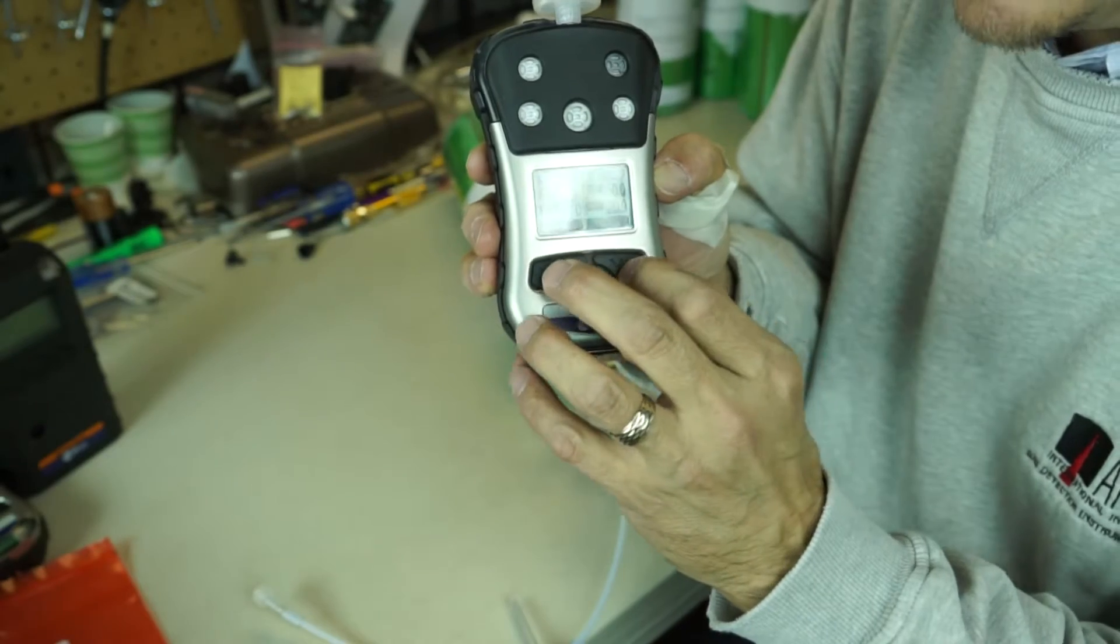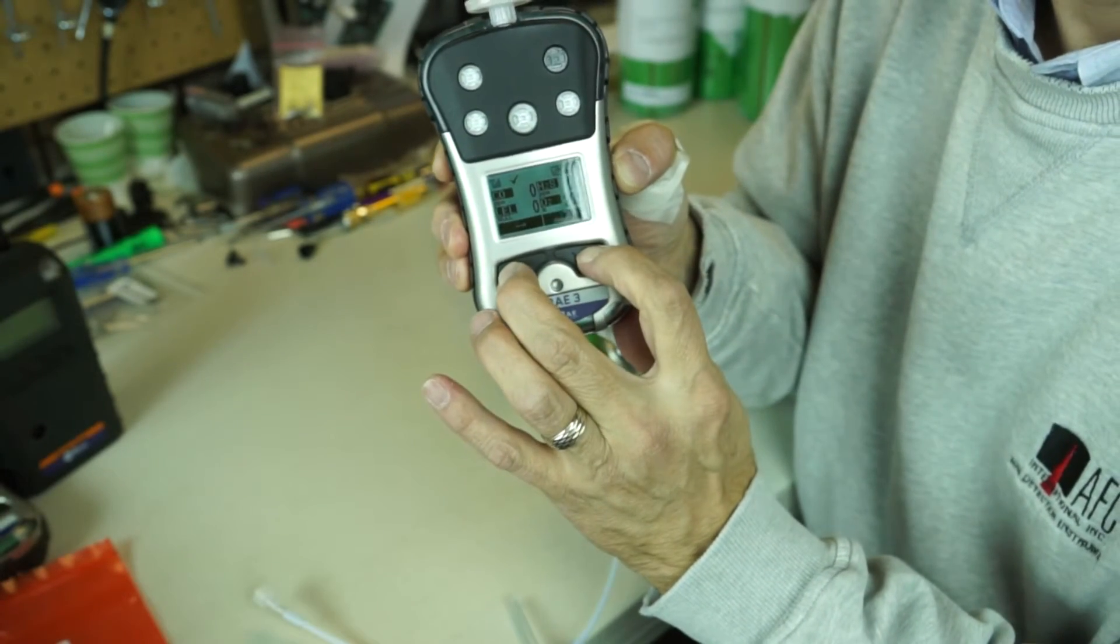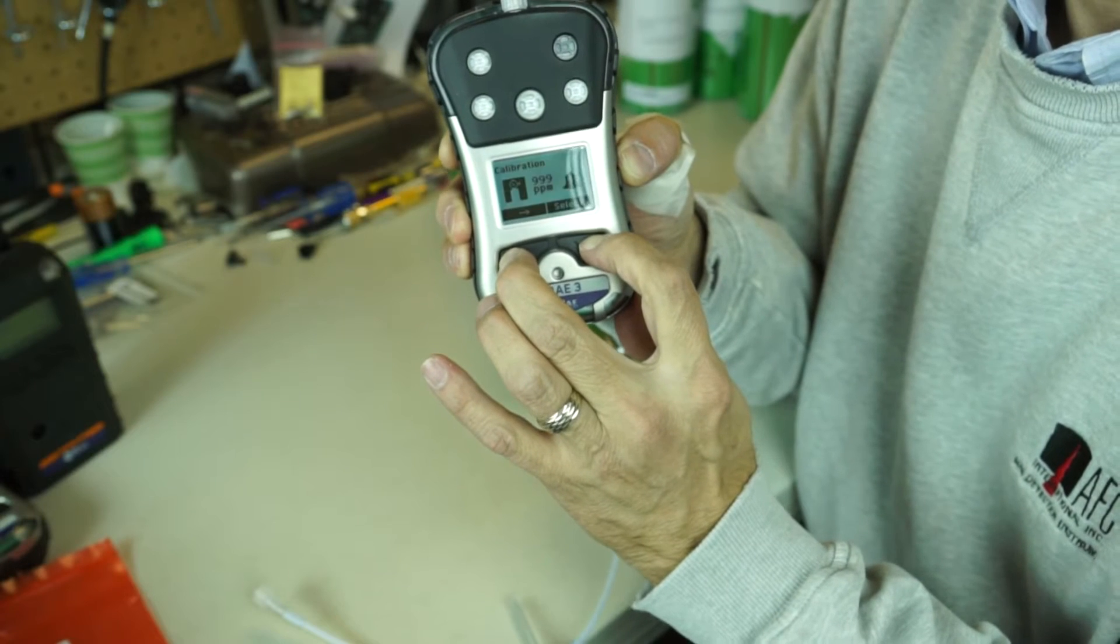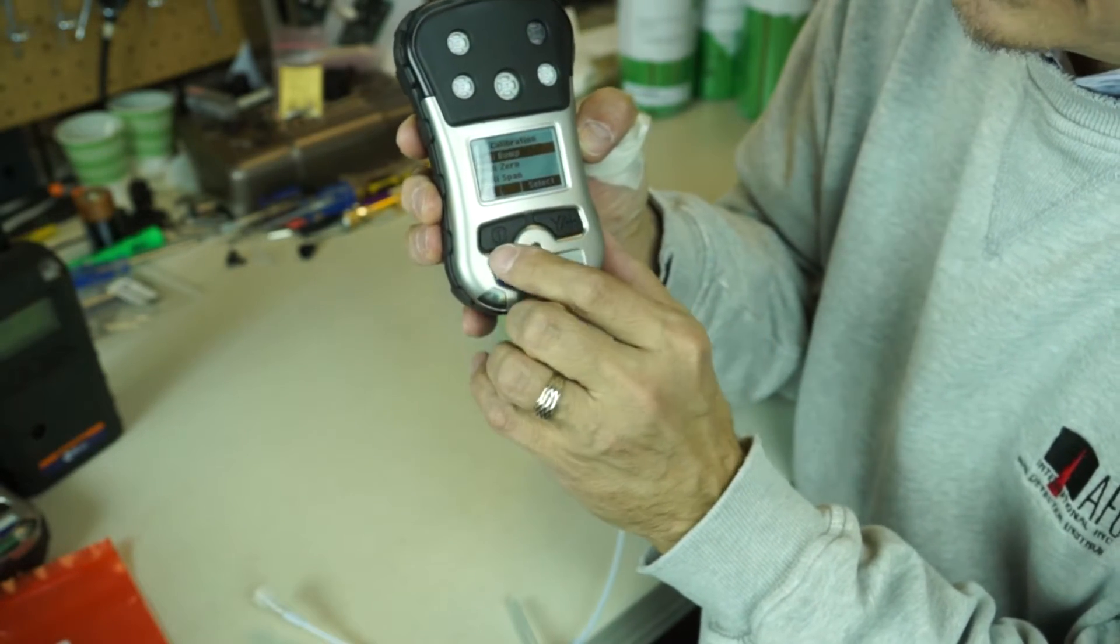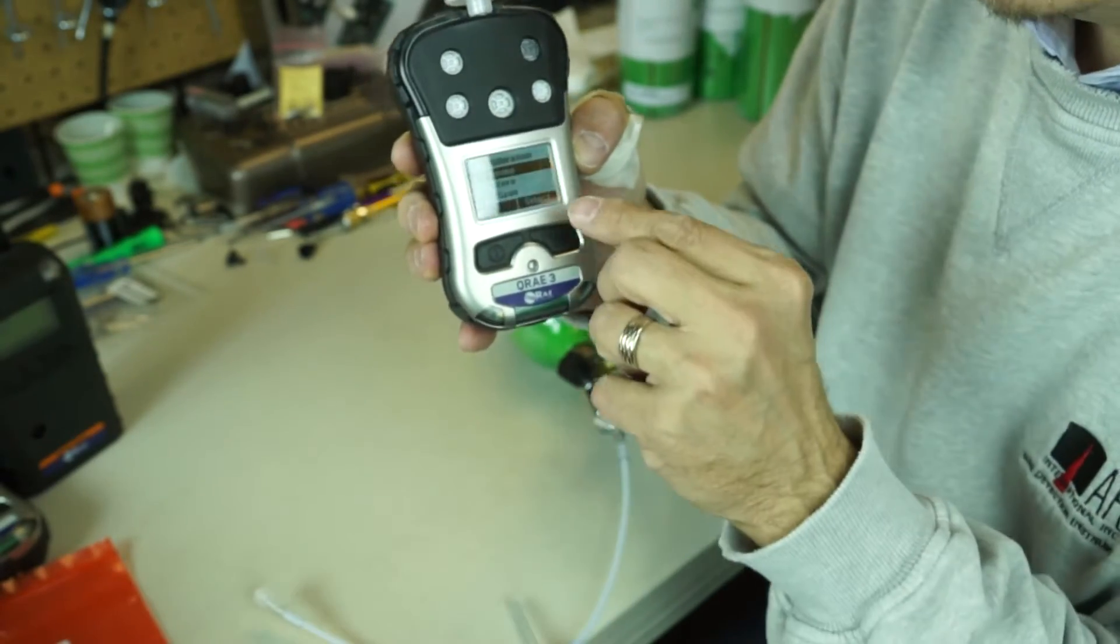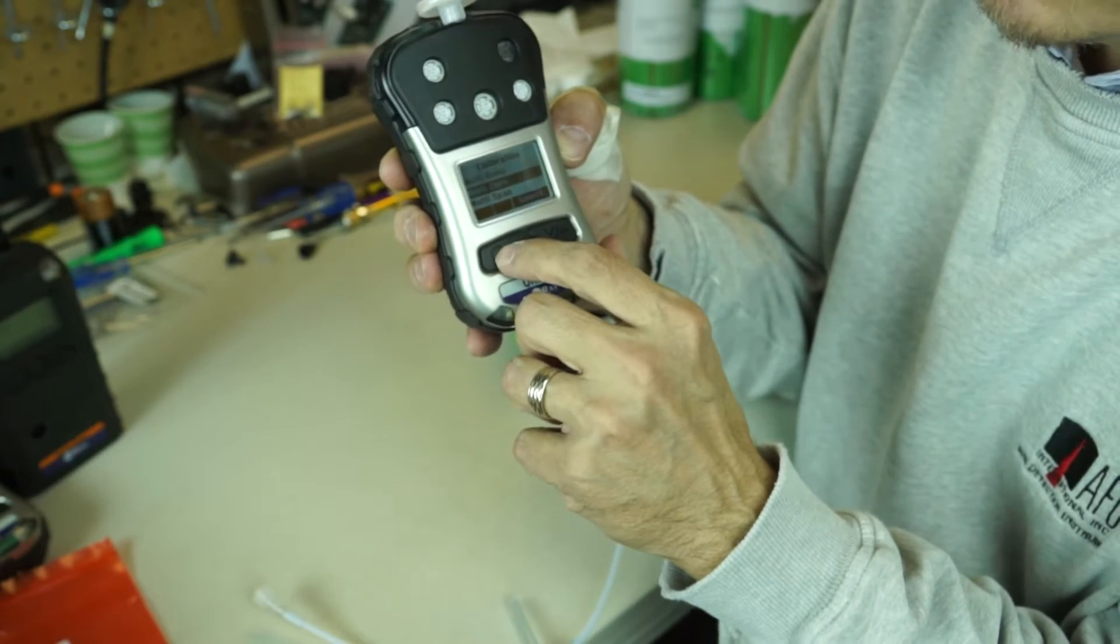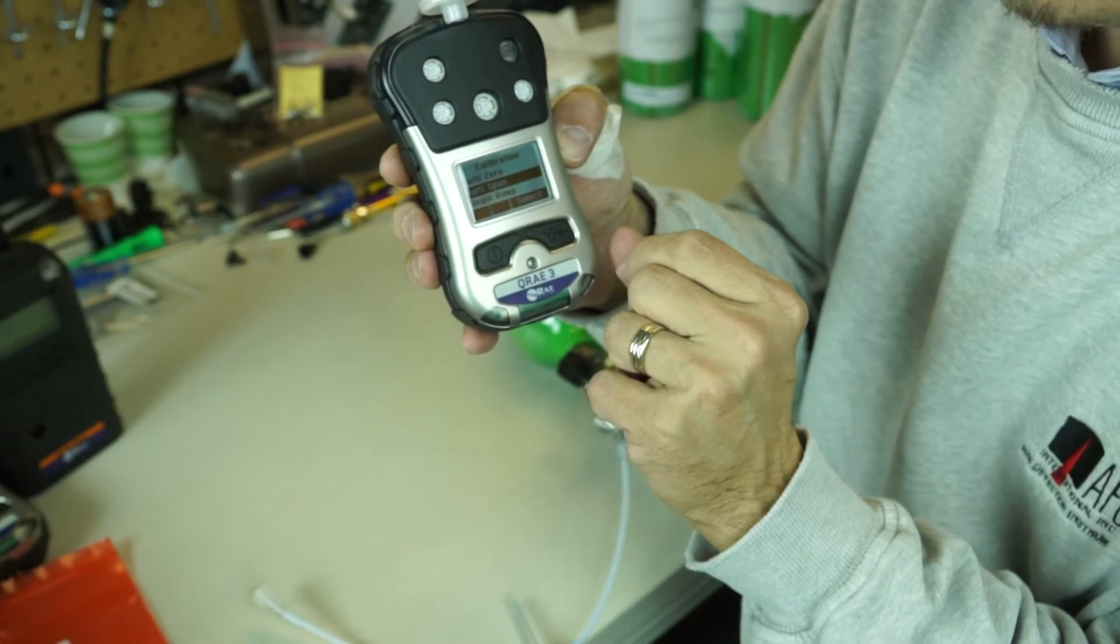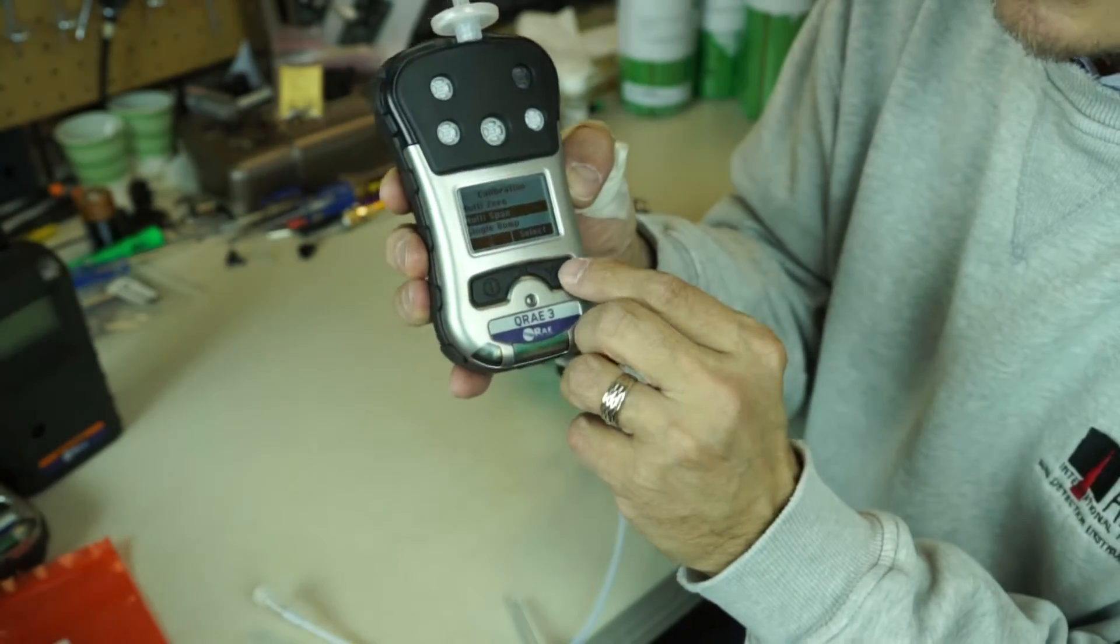And I'm going to go ahead and get into the calibration mode. On RAE systems it's mode in no, or mode in yes in this case. And it's going to ask me for a password. Sometimes if it's not password protected you can go right into the calibration. And you'll scroll down until you see multi-span. Can you see that? Multi-span. I'm going to hit yes and select.